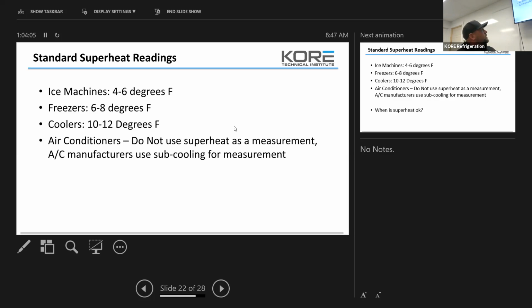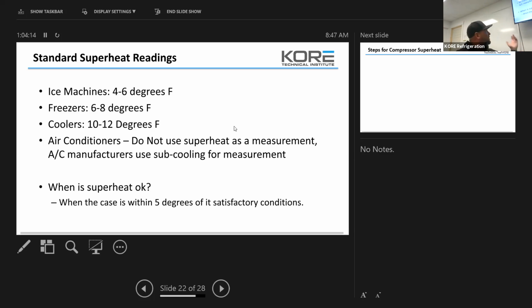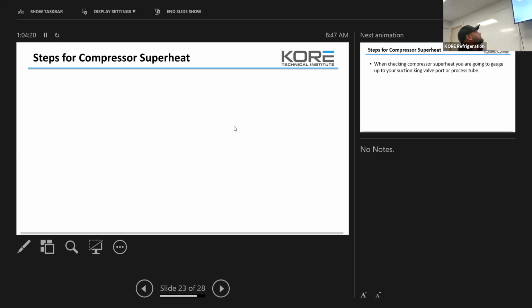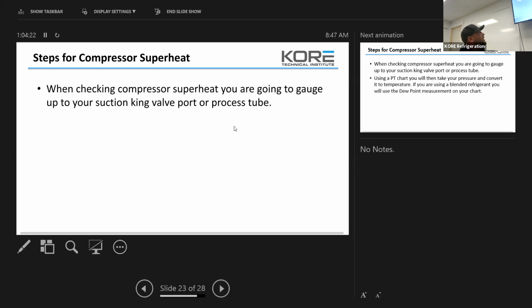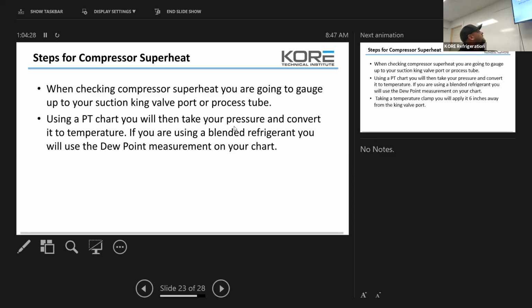Air conditioners do not use superheat as a measurement. AC manufacturers use subcooling for a measurement. We talked about that. So with superheat, it's when the case is within 5 degrees of its satisfactory conditions or optimal running temperatures. When checking compressor superheat, you're going to gauge up to your suction king valve port or process tube. You all know what the process tube is, right? On the can compressors, that little Schrader port that sticks up that you can gauge up to on the compressor. That's your point if you don't have a king valve on the compressor. On your smaller compressors, that's your crankcase pressure. That's going to tell you what your suction pressure is right there at the compressor.